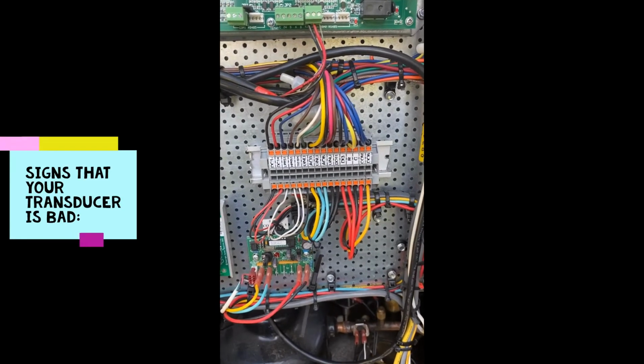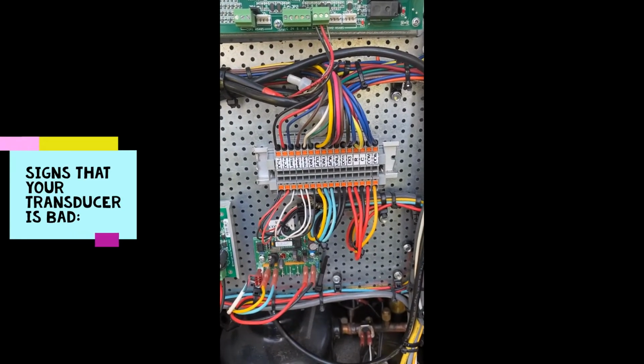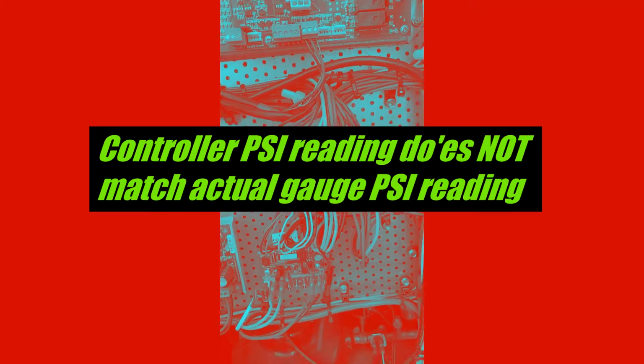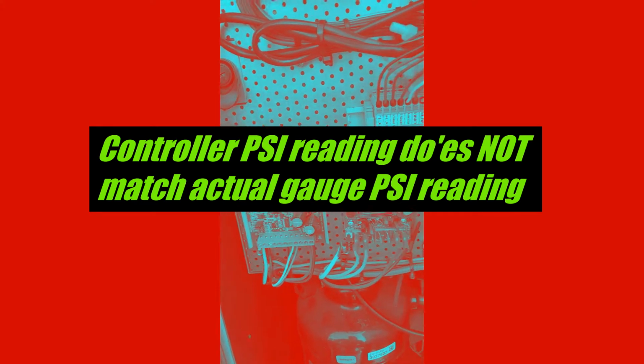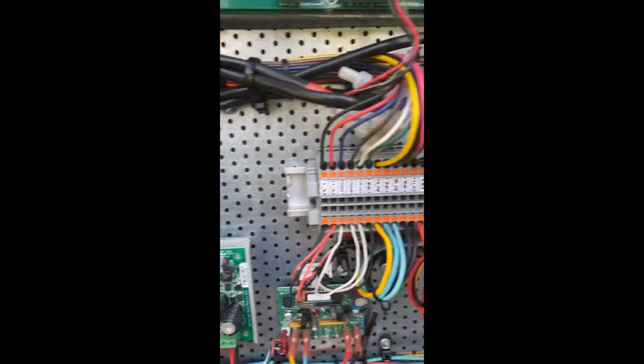Alright, so how do we know our suction transducer is bad and not the board or not something else? So when I arrived, my controller was telling me that my suction temperature was negative 13 degrees. That's the first sign. And it wasn't moving up or down, it wasn't changing, it was just a stable negative 13. Then the condenser would run for a little bit, turn off on low pressure, even though the refrigerant pressures were normal. So that's one thing you got to check, that you're not actually going off on low pressure. So I had a low pressure alarm.